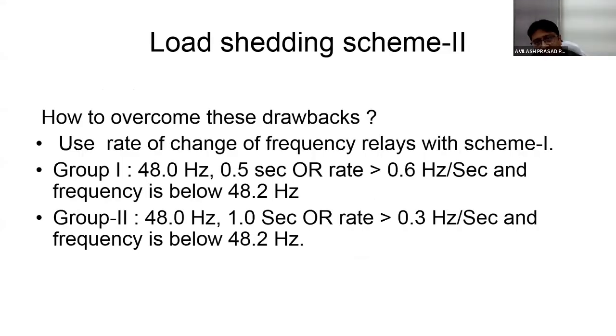So there is an alternative load shedding scheme too. Then how to overcome these drawbacks? We have devised an alternative load shedding scheme, that is scheme 2, where we use rate of change of frequency relays with scheme 1. In this scheme, group 1: if frequency drops to 48 Hz for 0.5 second, or at a rate of 0.6 Hz per second and frequency is below 48.2 Hz. In group 2: frequency 48 Hz for 1 second, or rate greater than 0.3 Hz per second and frequency is below 48.2 Hz.